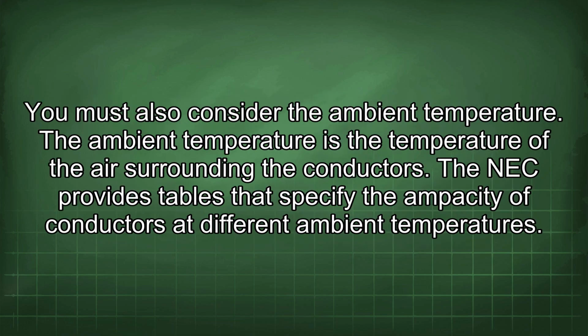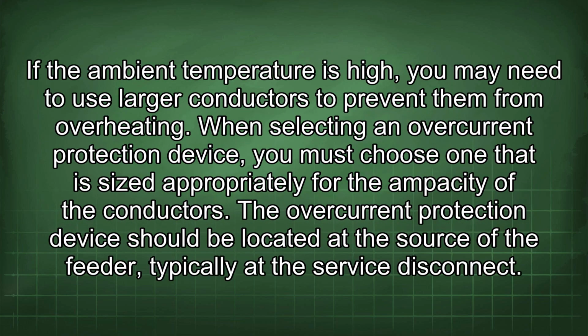You must also consider the ambient temperature. The ambient temperature is the temperature of the air surrounding the conductors. The NEC provides tables that specify the ampacity of conductors at different ambient temperatures. If the ambient temperature is high, you may need to use larger conductors to prevent them from overheating.